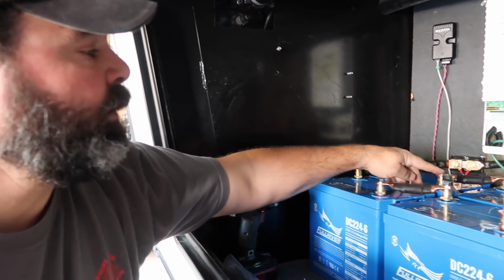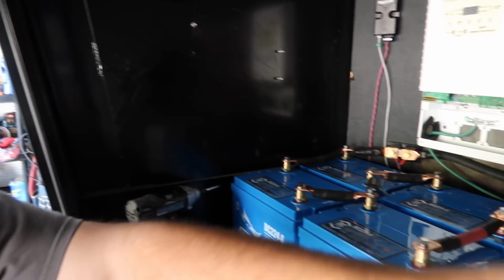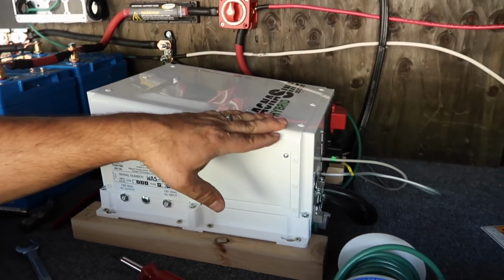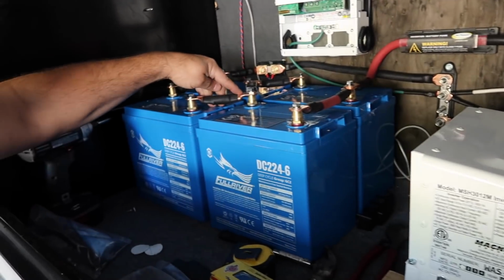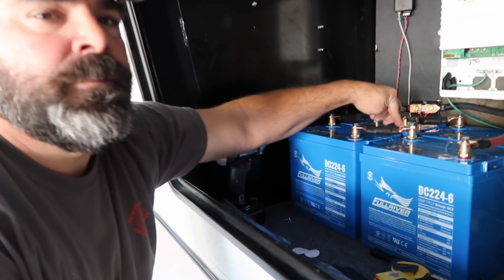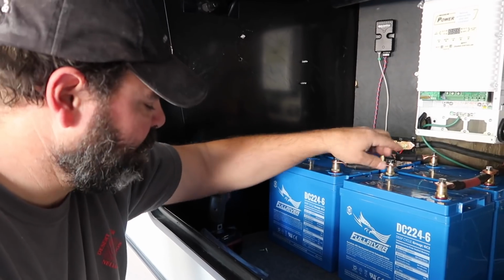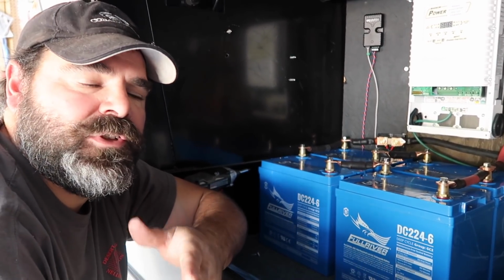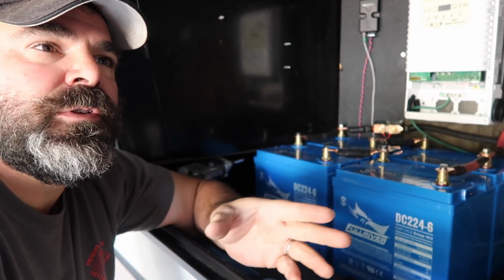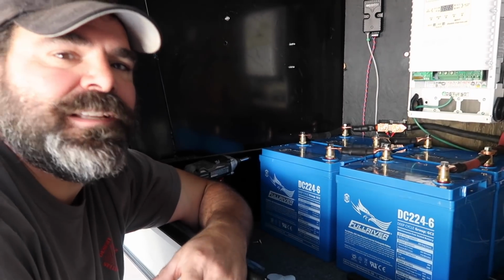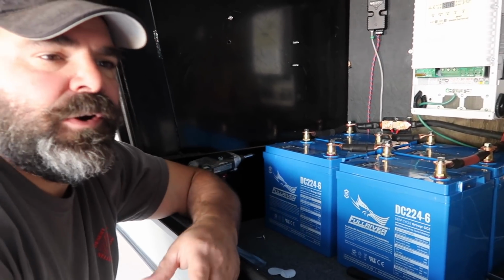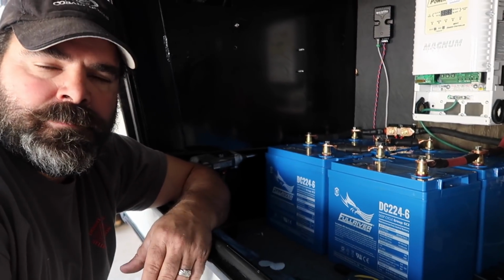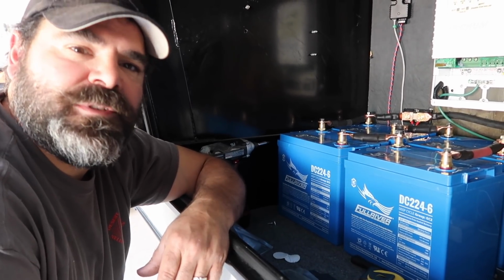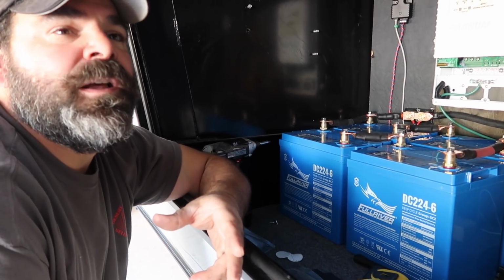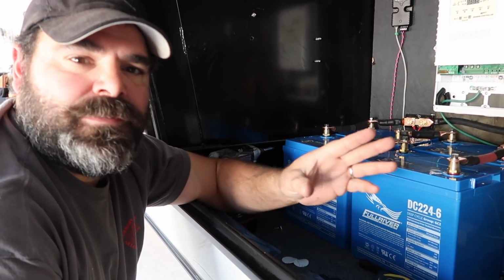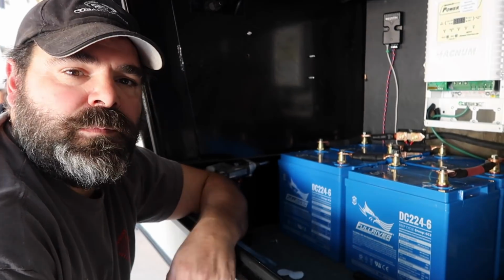Also, part of the temperature sensor - you saw how I plugged the temperature sensor in on the back side of the hybrid over here. Well, the cable runs and attaches to a negative post on the batteries. What the temperature sensor does is adjust the charger's battery charging profile based on the temperature of the batteries, if they're over or under a certain point. So it's kind of important to have that battery temperature sensor on there, just in case you're in a hot environment - you want to make sure your charger isn't going to fry your batteries even more. This will help with that issue.